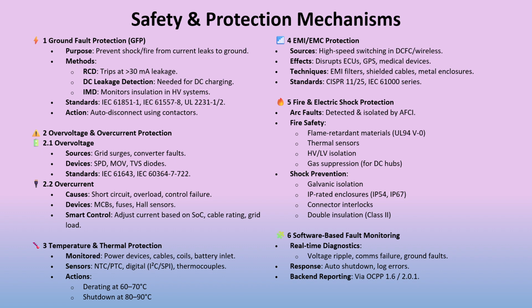Exactly. There's also EMC protection against electrical noise, fire retardant materials, isolation barriers, sealed enclosures, connector interlocks so you can't unplug under load, and software constantly running diagnostics, ready to shut down if it detects a fault. Puts your mind at ease knowing all that's going on.